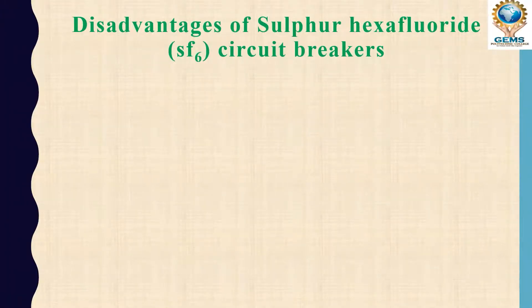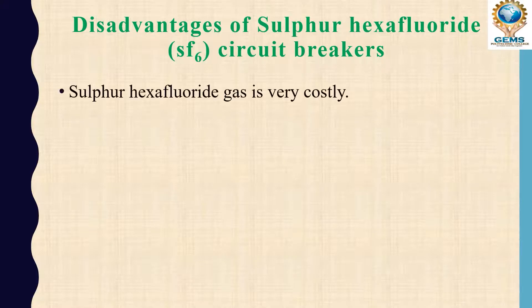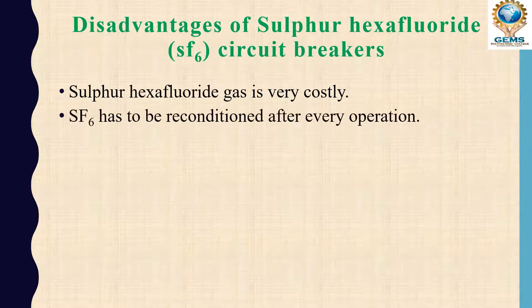Now if we see the disadvantages of the SF6 circuit breaker: the first disadvantage is that sulphur hexafluoride gas is very costly - we have to spend more money to purchase this gas. The second disadvantage is that SF6 gas has to be reconditioned after every operation.